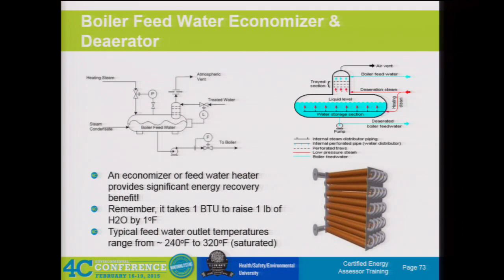Next we're going to go through some of these other components of the system that the rule requires we look at for an energy assessment—these are the parts of the overall energy generation and delivery systems. So we've kind of talked about the boiler area—boiler feed water, economizer, and deaerator. In a boiler situation, the feed water system is very important to how the boiler performs and the overall operation and efficiency of the unit. The boiler feed water typically has a deaerator in that process.